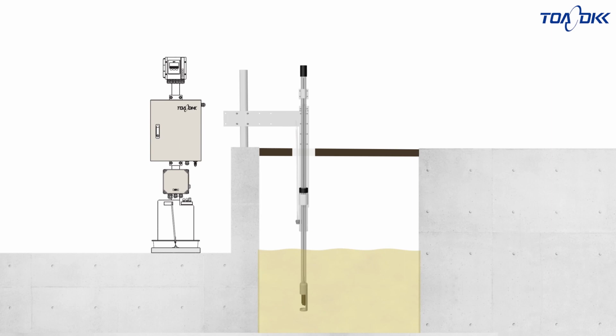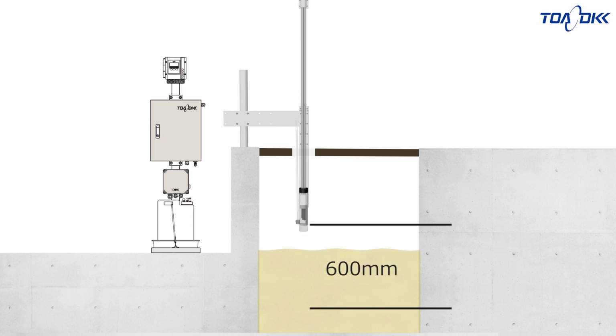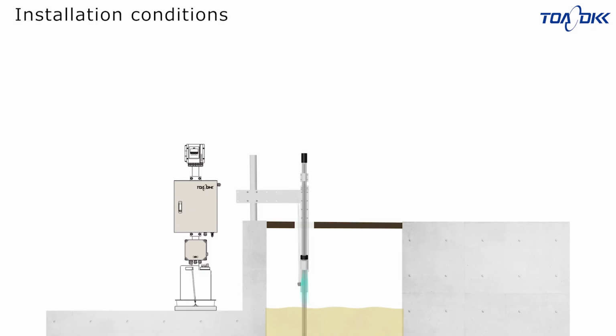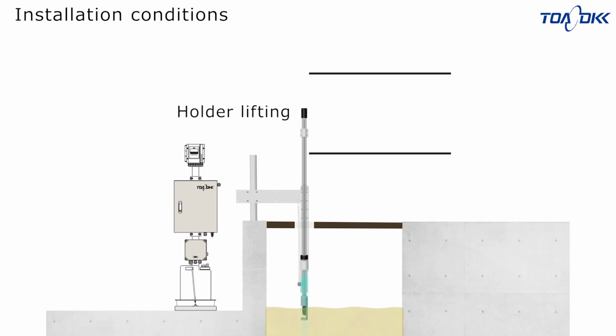During cleaning and calibration, the air cylinder rises the holder. Stroke length is 600 millimeters. Make sure there is enough space above the detector to allow the electrode holder to be pulled out upwards. In addition to stroke length, an additional height is required for removal.